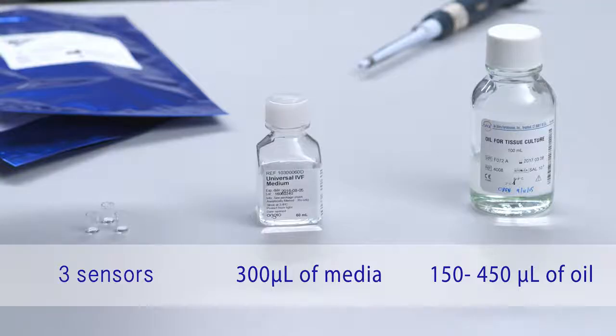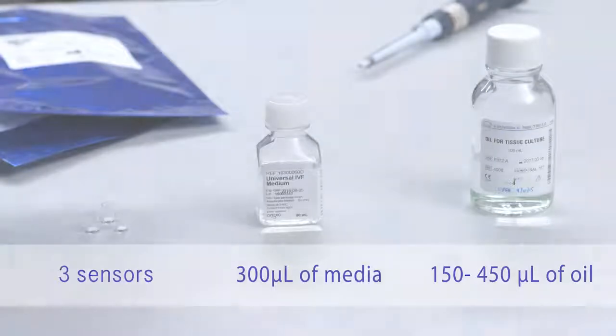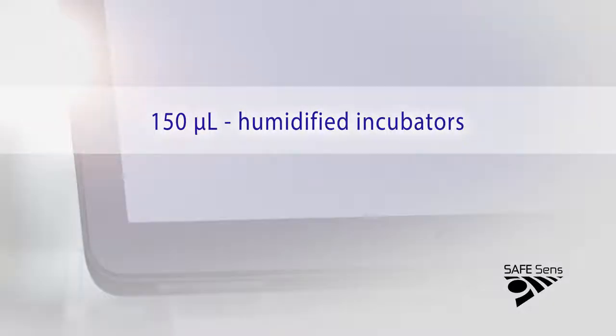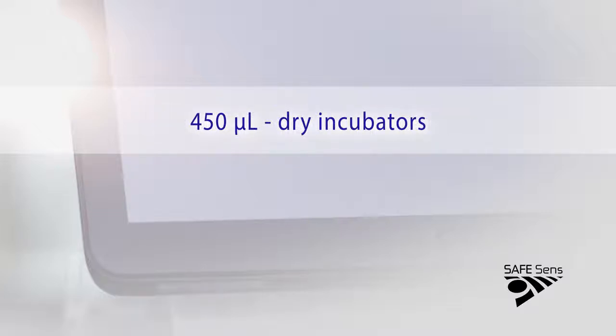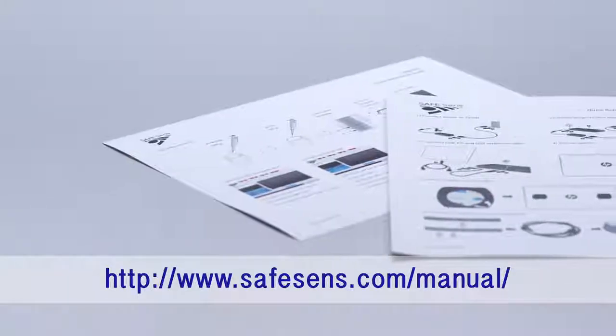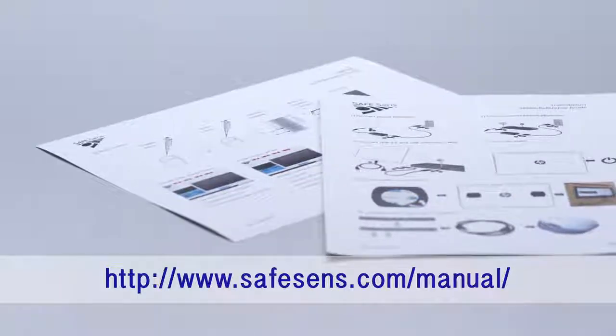Once you have your TrakStation and TrakPods installed and QC tested, gather the required materials. You will need 3 sensors, 300 microliters of media, and oil for overlay. You will need 150 microliters of oil for humidified incubators or 450 microliters of oil for dry incubators. Plan for 5 minutes of setup time in the afternoon and 10 minutes the next day to perform the pH readings. If you want to follow along, the protocol is in the first time use section of the user's manual.